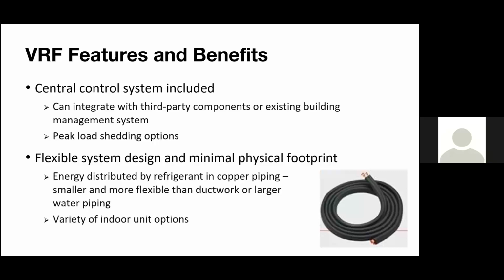It's a mix of larger hard copper lines, around an inch and a half, which are the largest lines you'll really see. And you'll also see what we call line sets, or soft copper lines that are usually small, quarter inch, maybe 3/8, that are rolled up, similar to the image shown in the bottom right here. You can unroll and flexibly route them throughout the building. Then of course we have all sorts of indoor unit options as well that we'll touch on in a few slides, which provides lots of flexibility.